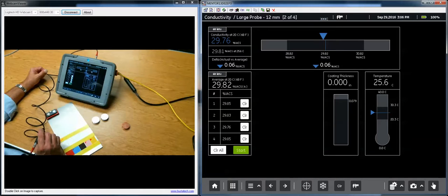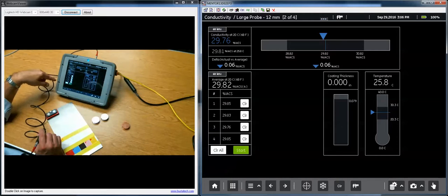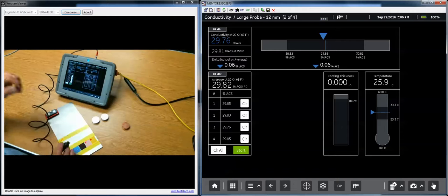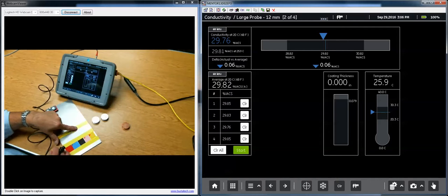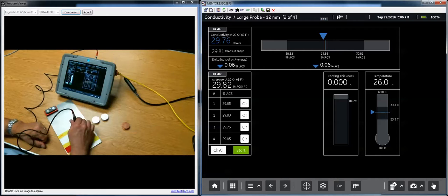Now I'm in an acceptable range again. And there's an audible alarm that's available for the instrument. Many of the current conductivity modules have a beeper in them, so you could have it beep when it detects something out of range. If you notice, I have some plastic shims and some tape on my aluminum sample here to simulate paint. The tape is about 7/1000ths of an inch thick.